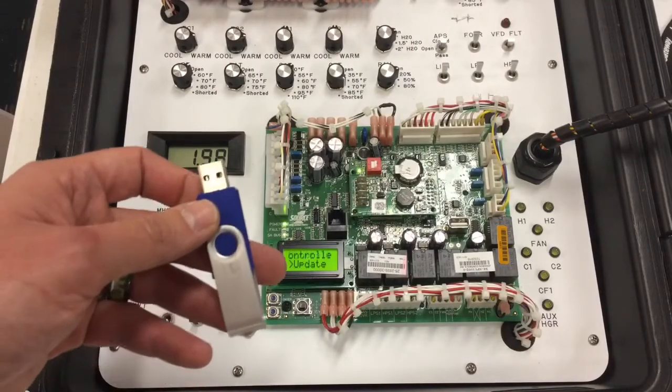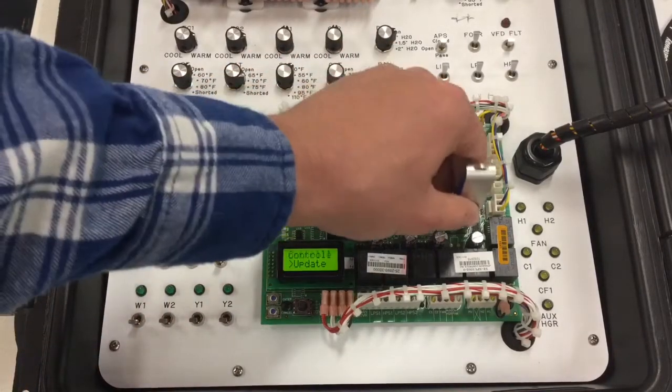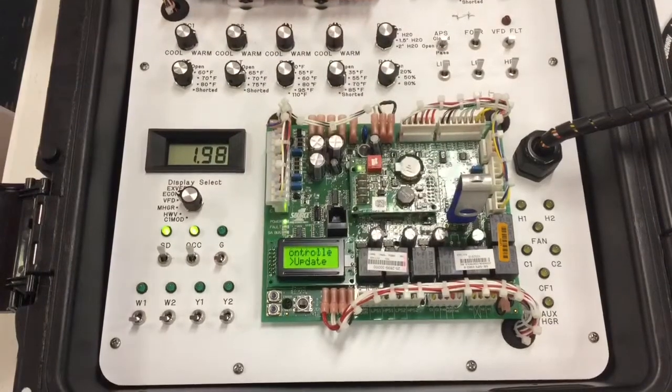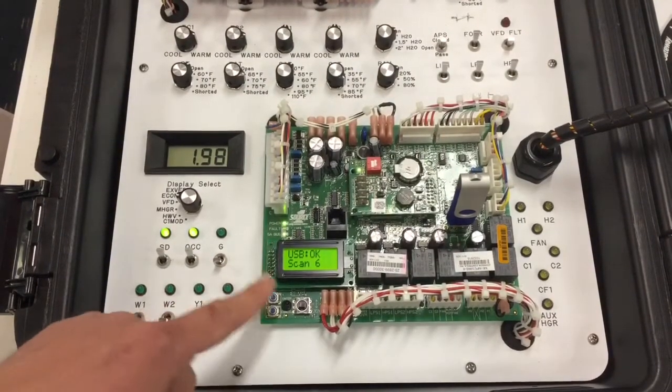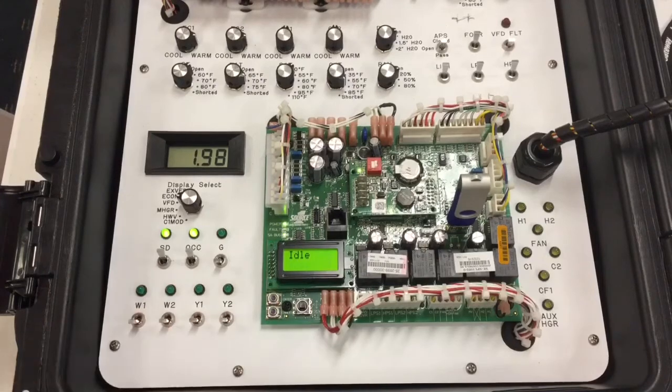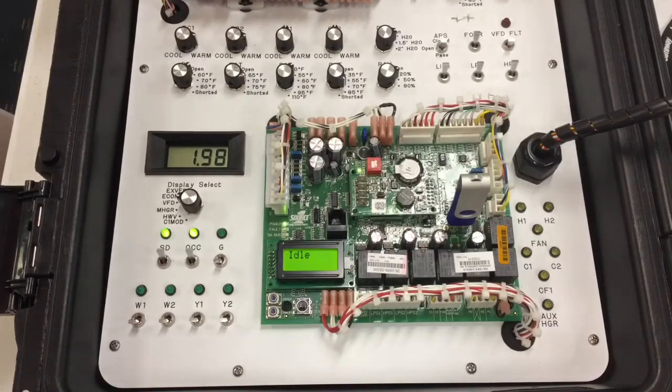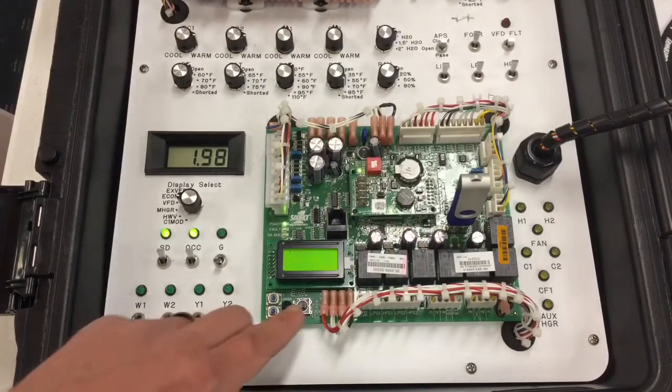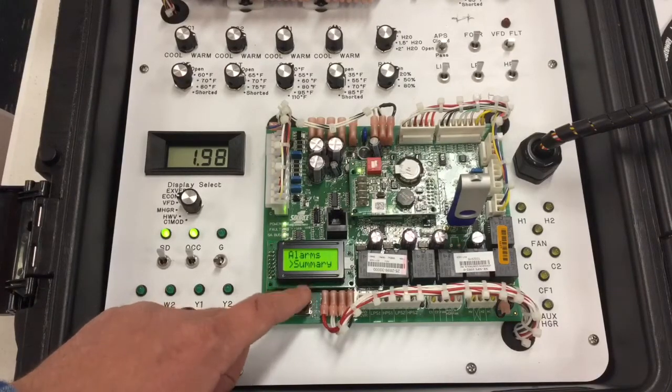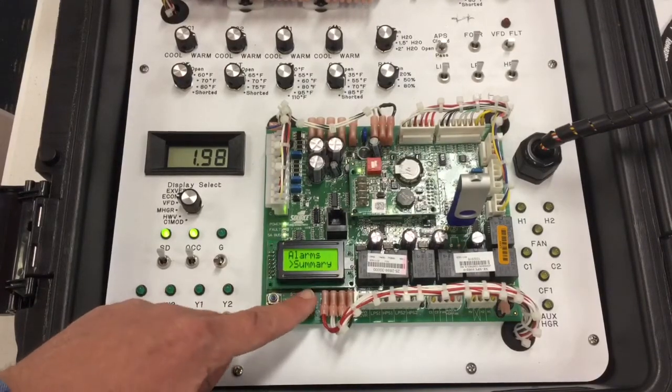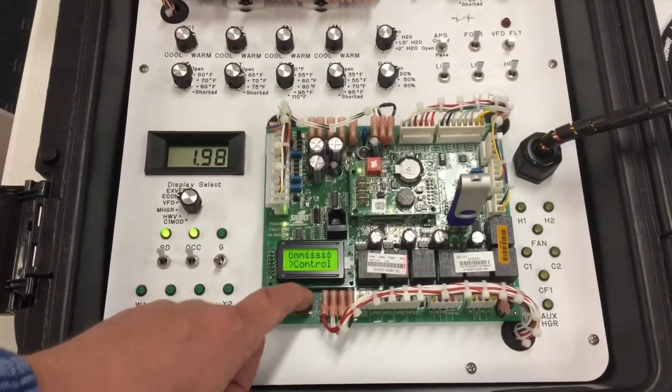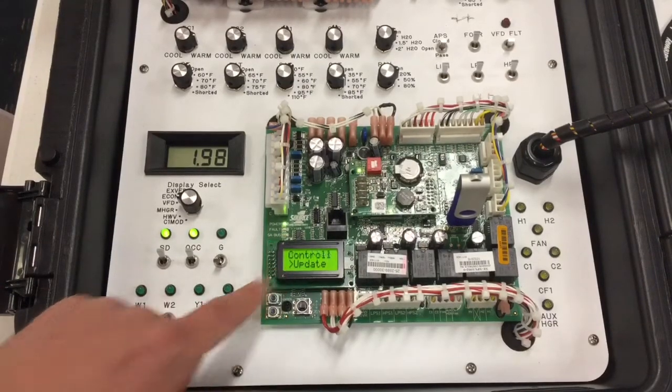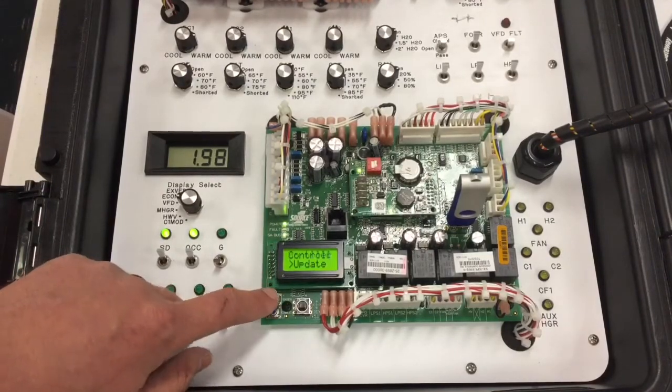I will take the USB drive and I will install it into the control board. If the flash drive has been read successfully, you'll see USB OK and then scan a number. In your case, the scan number may be different than mine here. I'm going to press the down button on the controller until my cursor gets next to an option called update. My cursor is now next to update. I'm going to press the enter button one time.